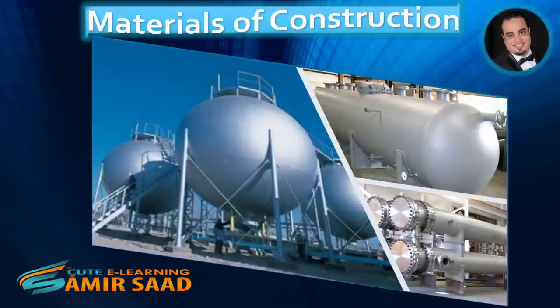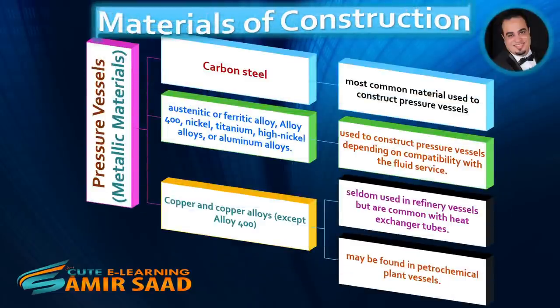We will discuss and focus on the materials used to construct pressure vessels and heat exchangers. Pressure vessels constructed out of metallic materials are made from: first, carbon steel, which is the most common material used; second, austenitic or ferritic alloy, Alloy 400, nickel, titanium, high nickel alloys, or aluminum alloys, depending on compatibility with the fluid service.